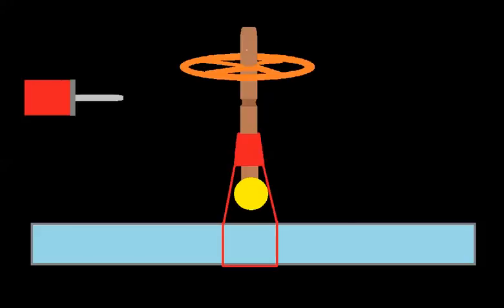This is called, this type of valve is an OS and Y. It's an outside stem and yoke. So this brown thing right here is the stem. And when you shut this valve, if you were to turn this wheel, this stem would start to go down. If it were closed, you could tell just by looking at it that this stem would be completely inside the red, I think that part is called the yoke.